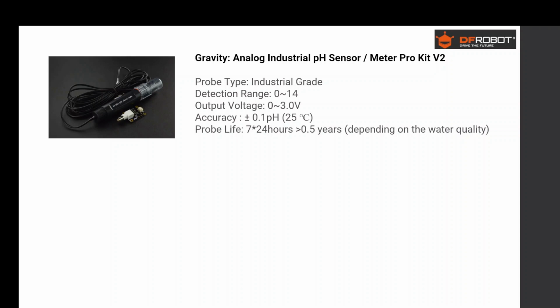It outputs a voltage of 0 to 3 volt in the range of 0 to 14 pH. So it's easy to calculate the pH value, and it has an accuracy of 0.1 pH. That's very good for an application like this. It's a very good sensor. It also includes an interface board, as you can see in the picture here. So just connect, calibrate, and start to use.